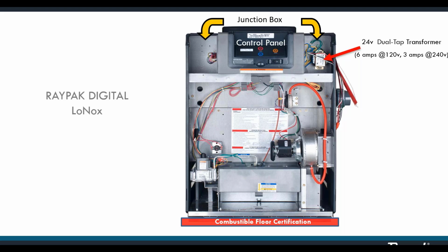So if you want to pull the conduit up on the left, you would take your transformer out on the right, 2 screws holding that in. Take that out, disconnect the wires, reinstall it on the left, and pull the wires back accordingly. You will notice there is another object in that junction box. That's our fan relay. Don't worry, there's still room in there for the transformer. I've moved transformers many times on the low NOx appliance. No problem at all. Heat barrier here keeps the heat downstairs where it belongs.